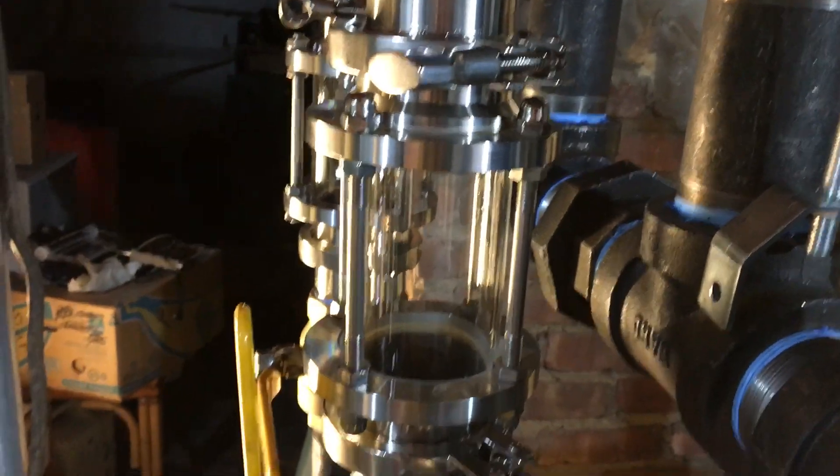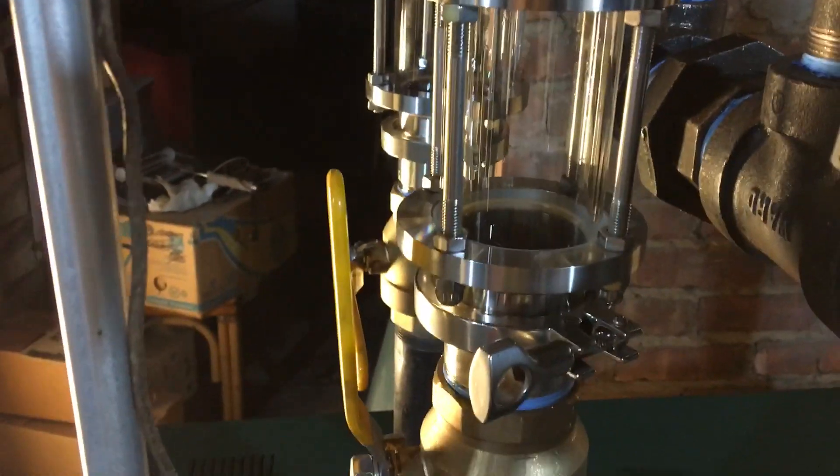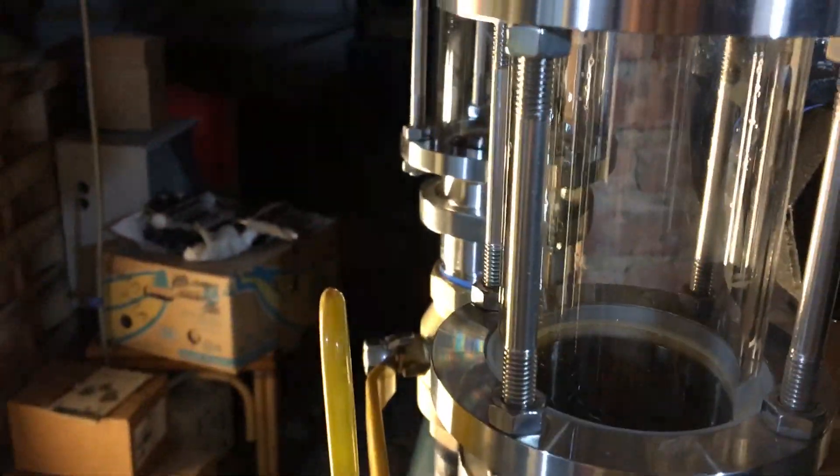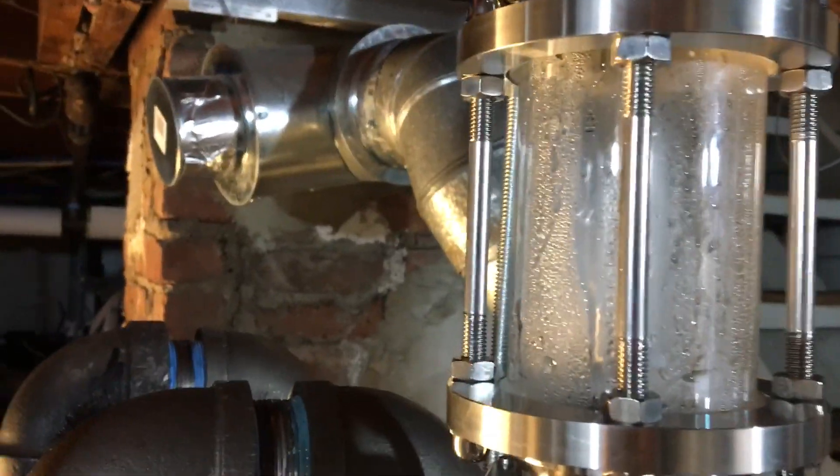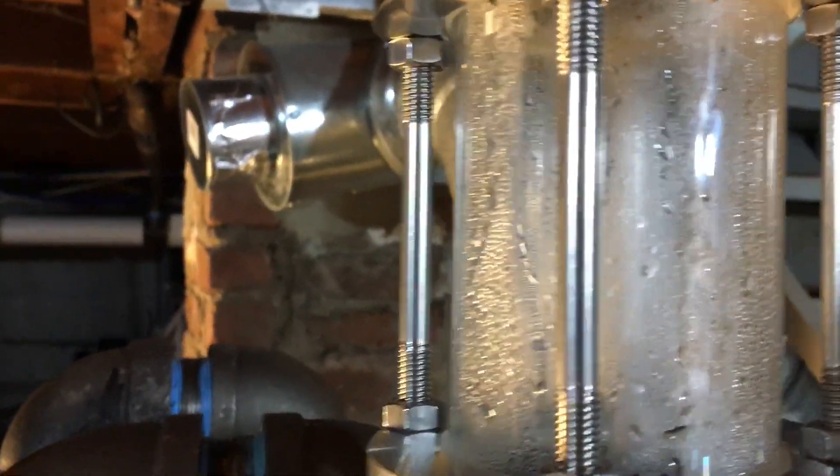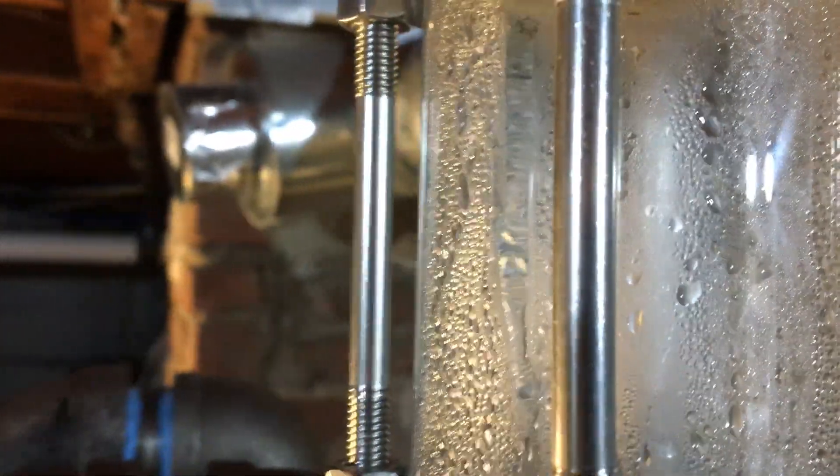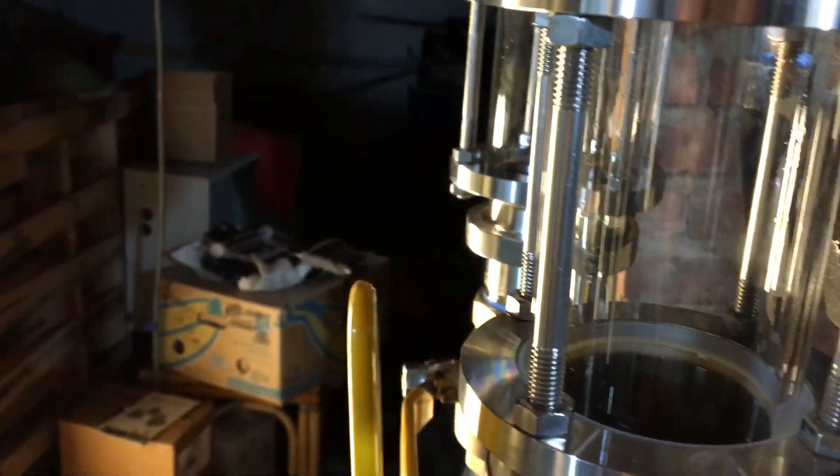With this one I have to really boost the water level to get it to throw any water at all, even up this high, and it's not going to get into the main, there's no way. I mean this glass is a little foggy but there's not going to be any water going up at this part of the header even if I were to boost the level even more.